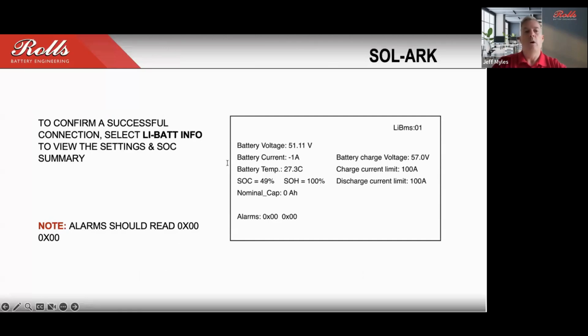So again, walking through that communication protocol, once that has been set properly, so you've selected, in this case, Sol-Ark from the dropdown, assigned the protocol, and you've completed that cable realignment and connected, then you're going to see this information displayed on the Sol-Ark display. Under the lithium battery info page, you'll be able to see the current and the battery temperature information. As soon as you see status information like temperature and state of charge, then you know that the system has been connected properly.